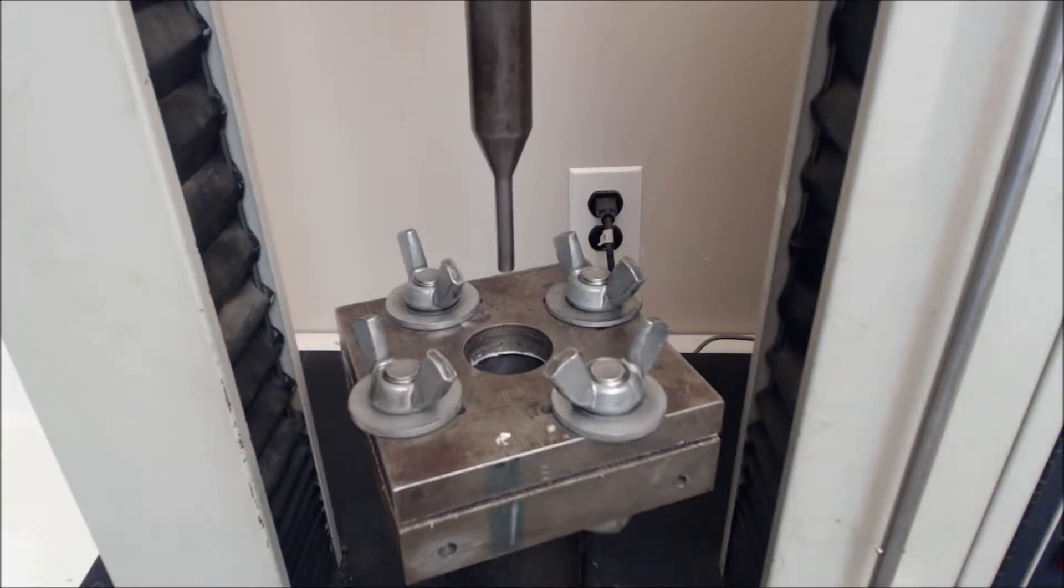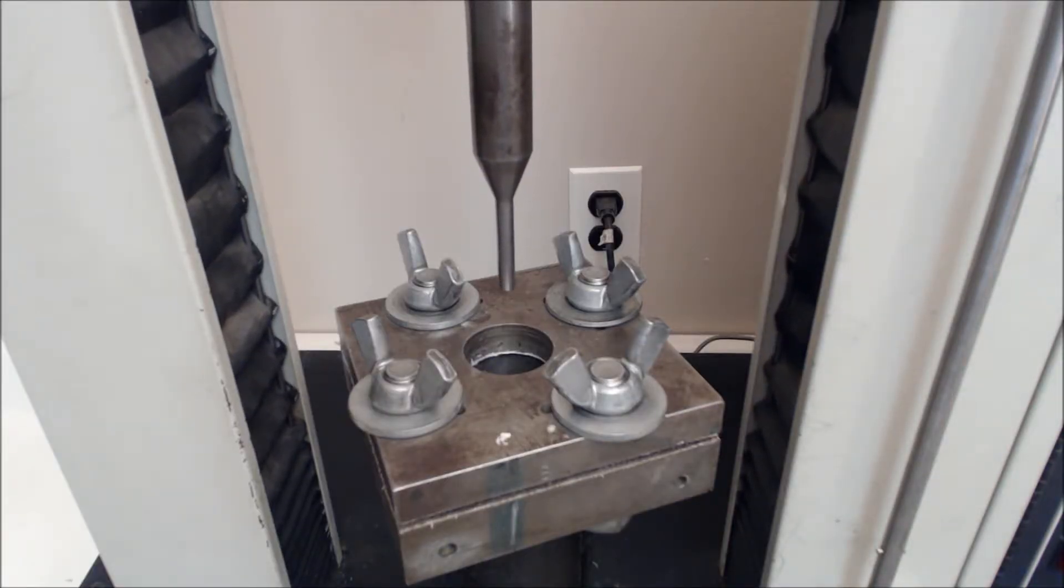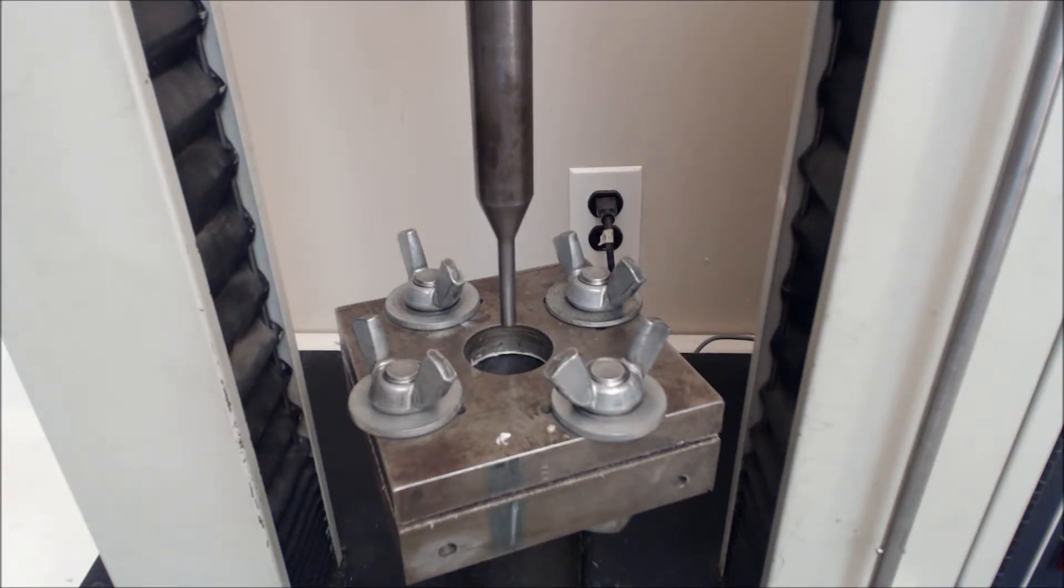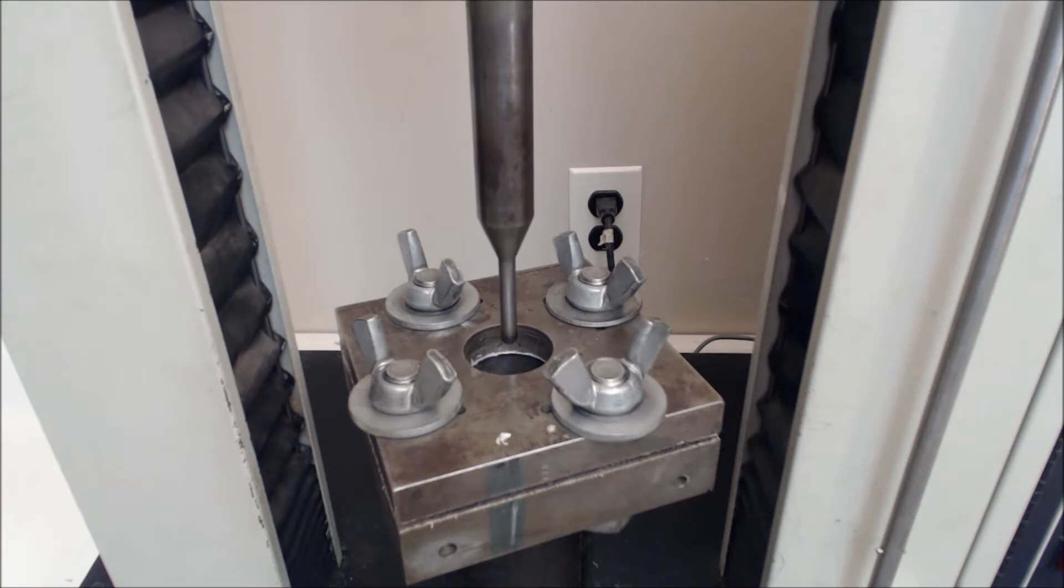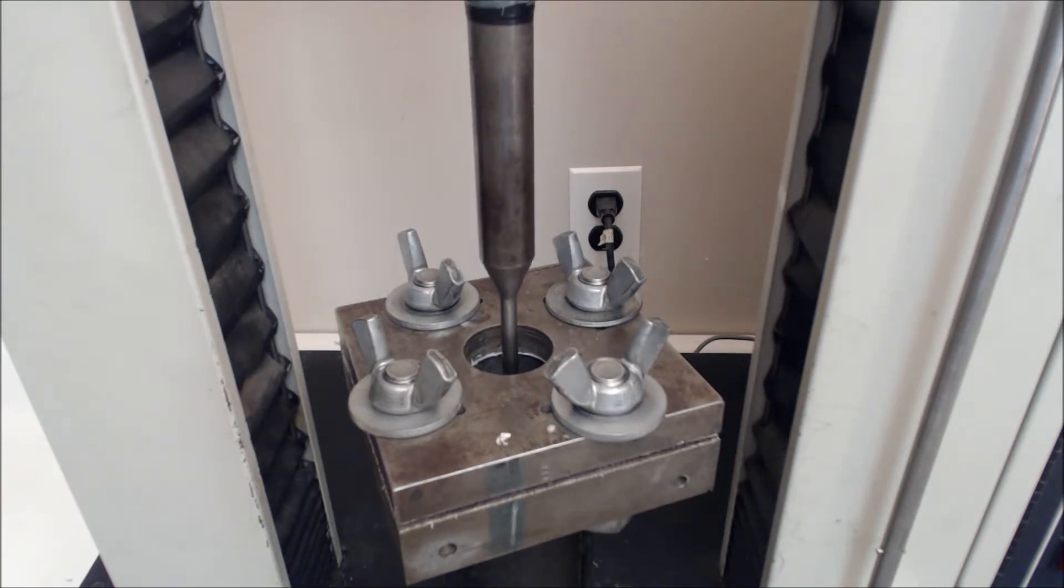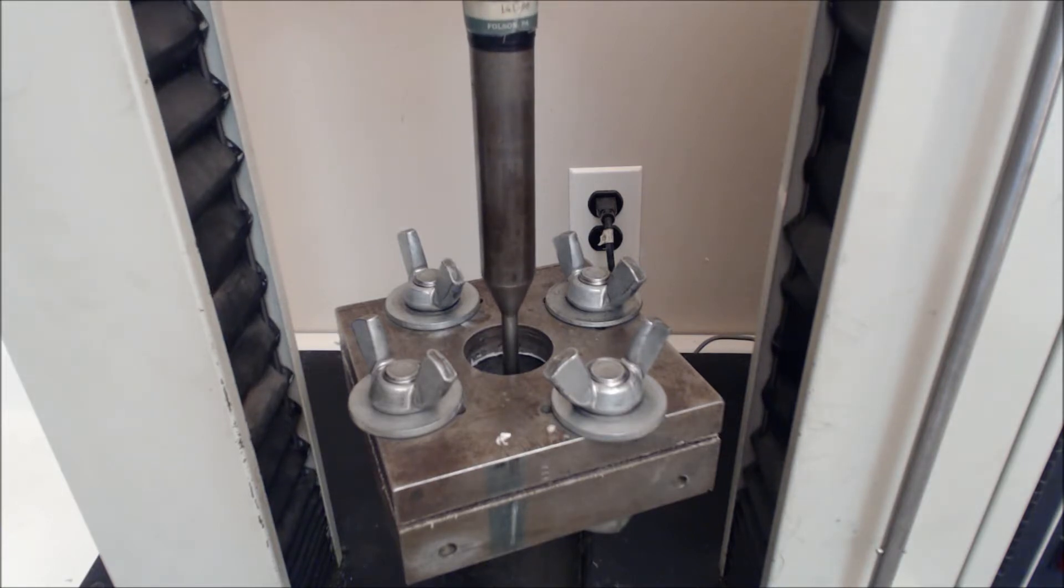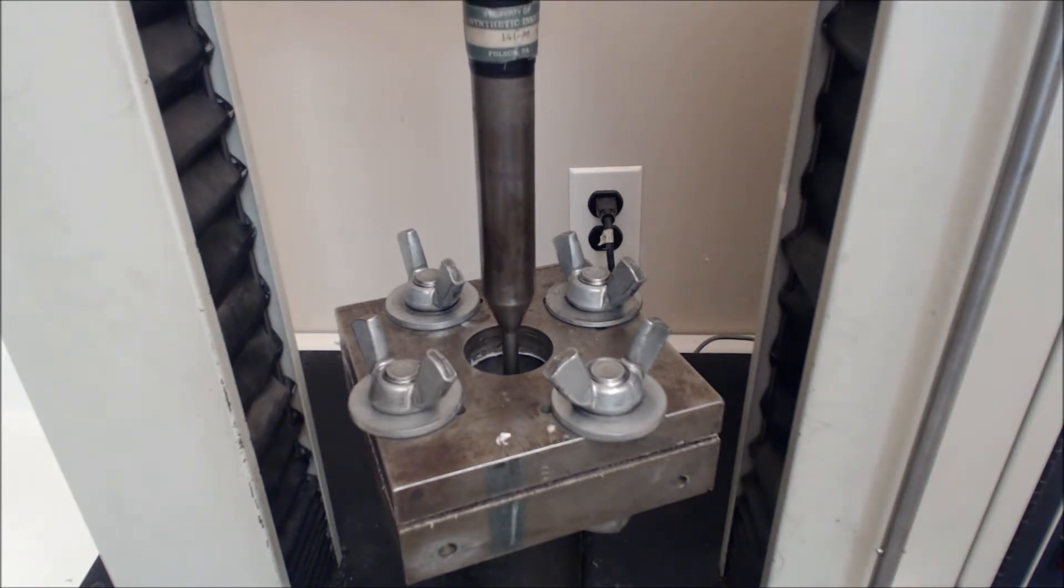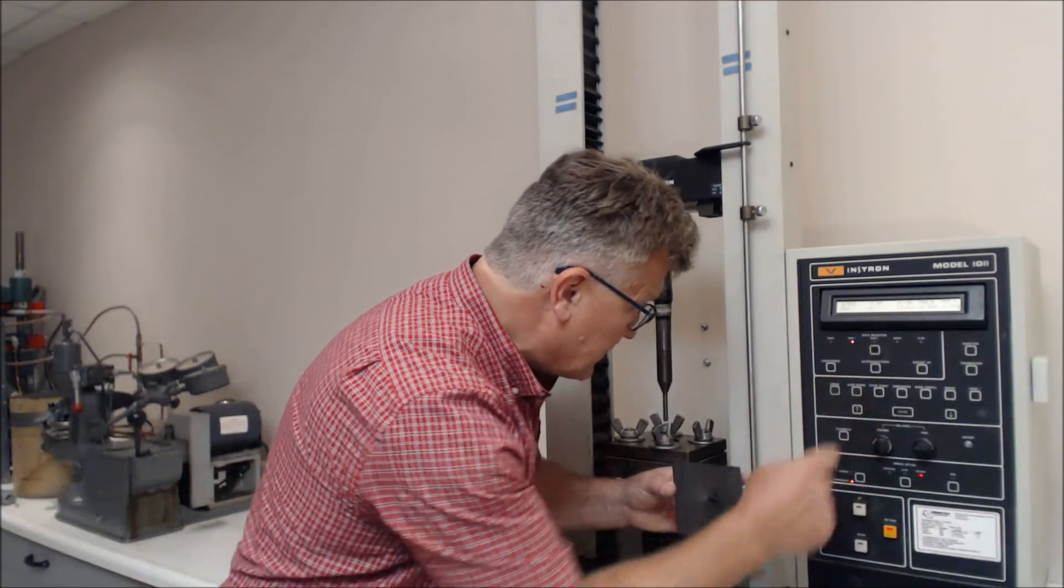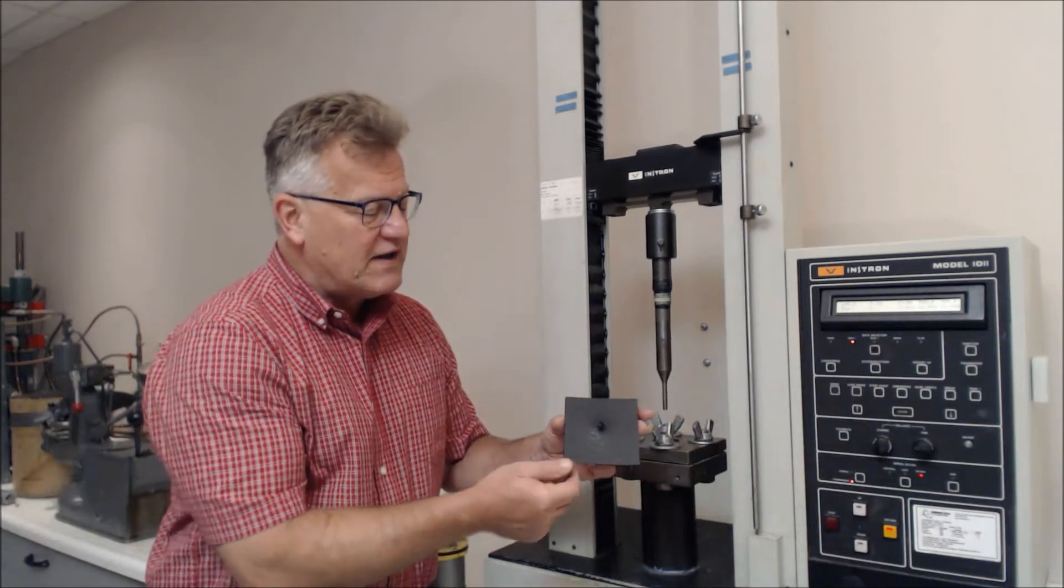Obviously, it has to be zeroed prior to starting the test, and you're looking for a maximum puncture strength of the device. You'll hear it. It's engaged now, and finally ruptured, and it gave a peak value of 145 pounds.